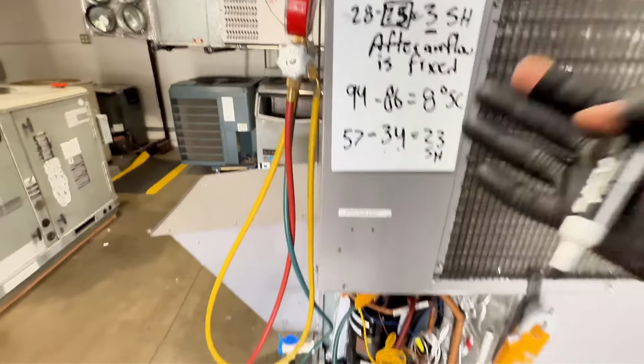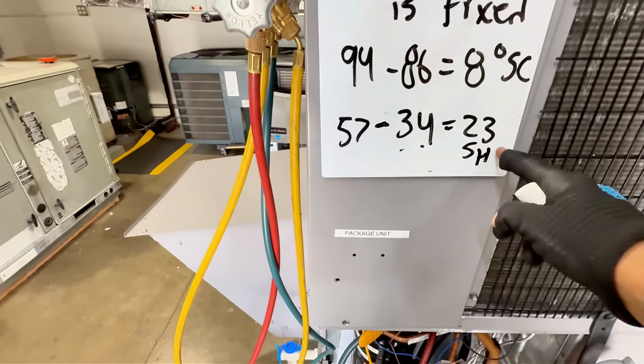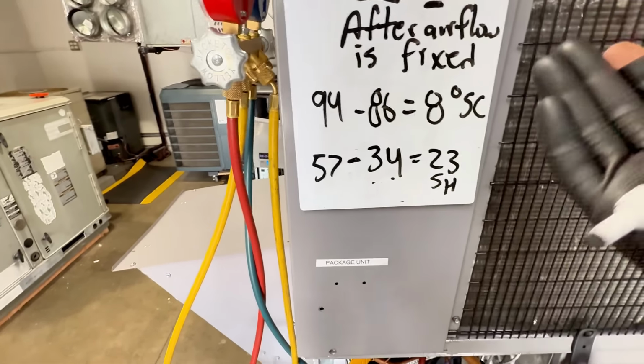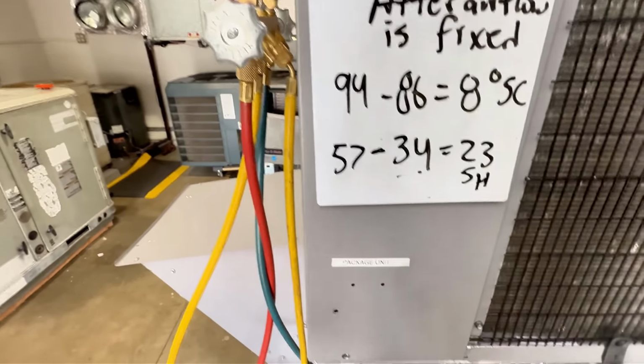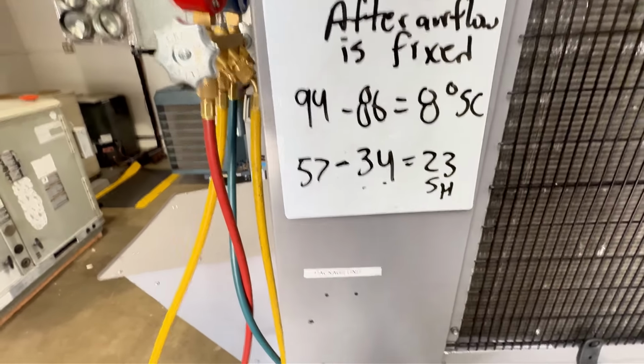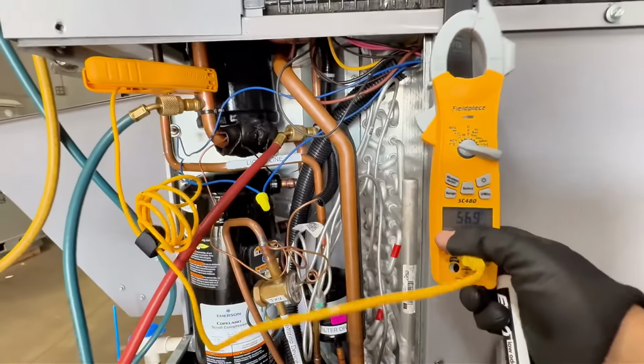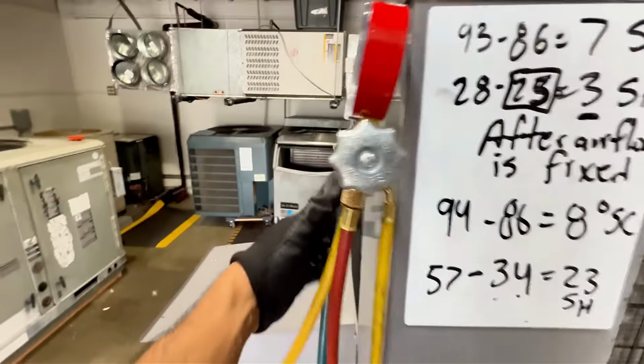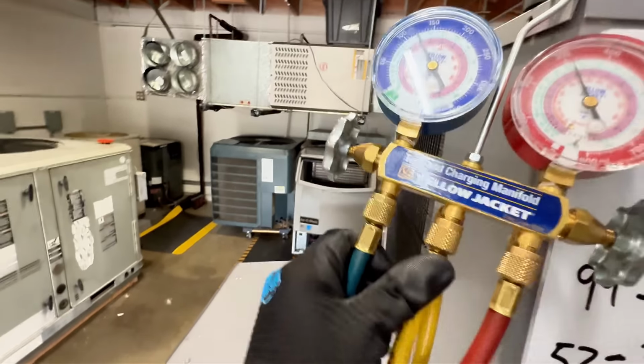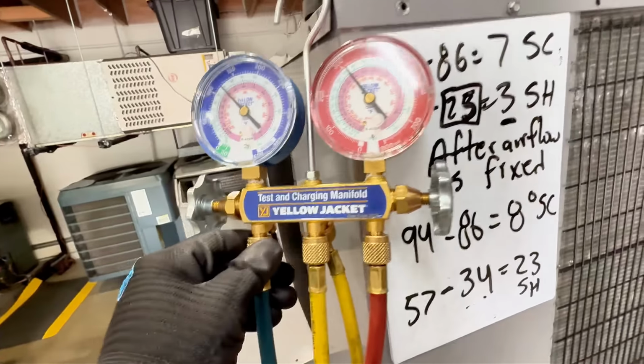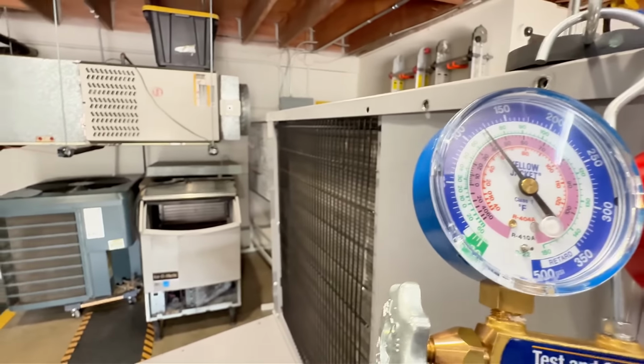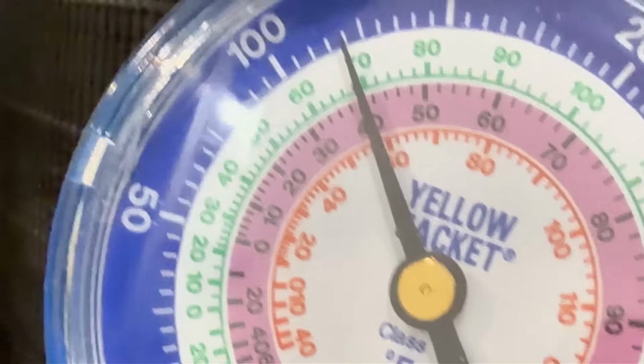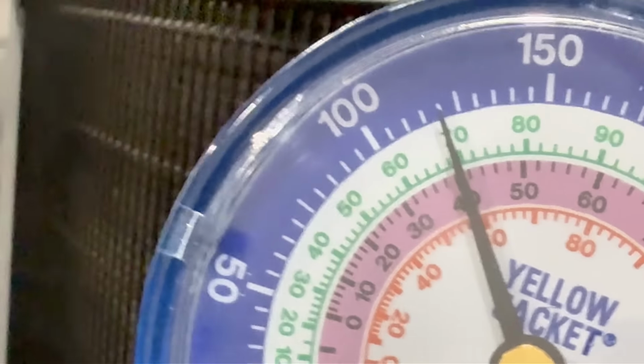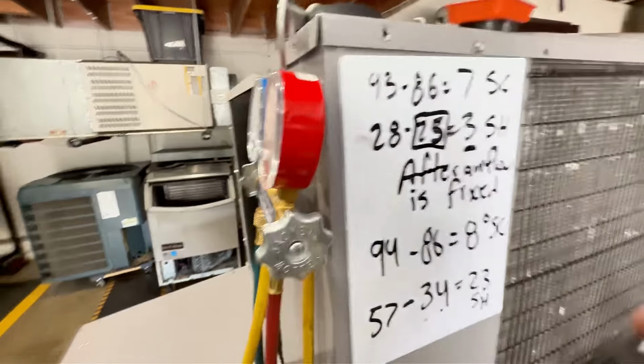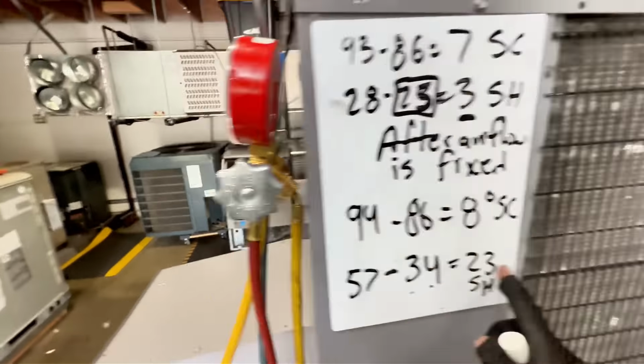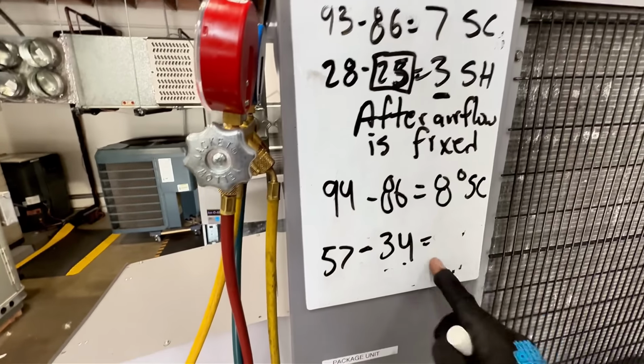So now that I introduced more air into the system, my superheat did go up, and it's at 23 degrees. So, am I happy with that? Not really. It should be a lot lower. Let's see if you are supposed to wait a little bit. Okay. So you see, this is why you wait a little bit, because we did fix the airflow issue. Now if you look, I'm at a 40 degree evaporator temperature. Let me take that back. 40 degrees. That's why you have to wait, because we did fix the airflow issue, right?